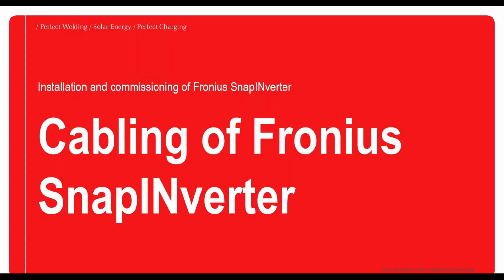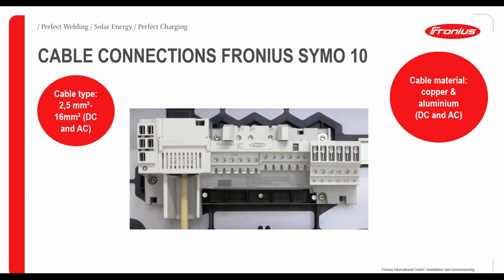After we fixed the wall mounting, we want to take a closer look on the cabling of the Fronius SnapInverter. Here I want to show you a connection compartment of a Symo, a big Symo, 10 kilowatt. In the red bubbles we can read cable diameters or cable dimensions can be put in from 2.5 square millimeters up to 16, both for AC and DC, and copper or aluminum can be used.